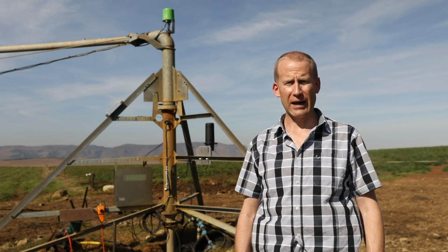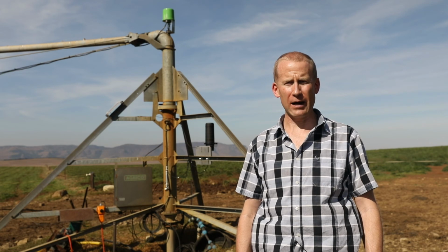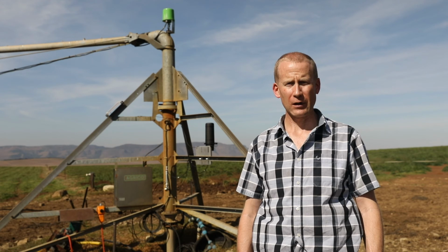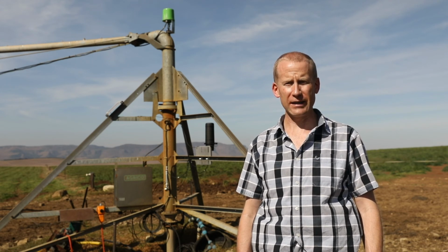After doing a thorough analysis, we advised Murray to change the pump and motor, upgrade the size of the pipeline, and install the pivot optimizer with a VSD. After doing that, the power consumption dropped down to 17 kilowatts, which was a saving of 56%. In conclusion, by optimizing the overall pumping system, very large energy savings can be achieved. More water can also be pumped by the same transformer.